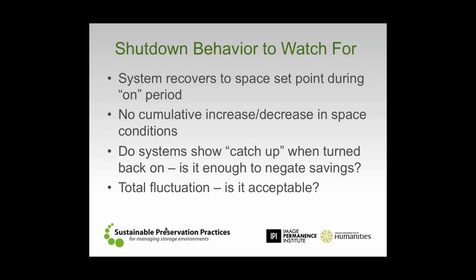We want to make sure that when we turn the system off and when we turn it back on, we recover to the set point for the space. We don't want to see ourselves losing condition in the space because of the shutdown. We want to make sure that if we were at 72 degrees when we turned it off, or if we were at 65 degrees when we turned it off, when we turn it on the next day, it ought to be able to get back to that 65 degrees.